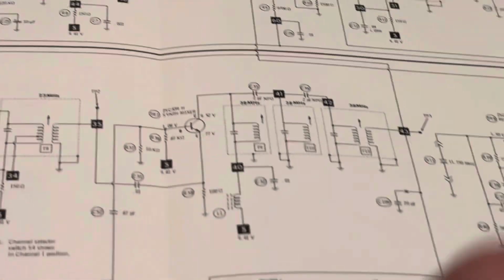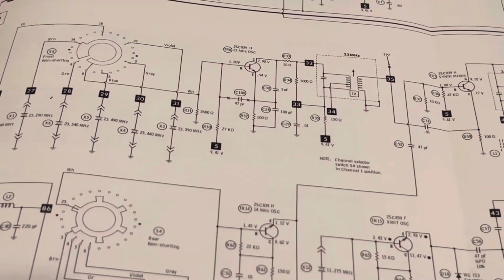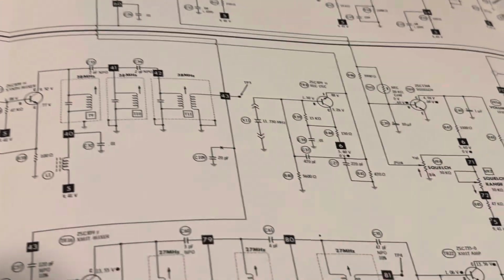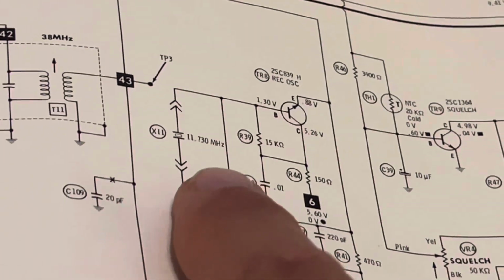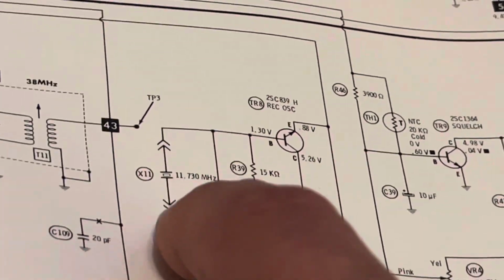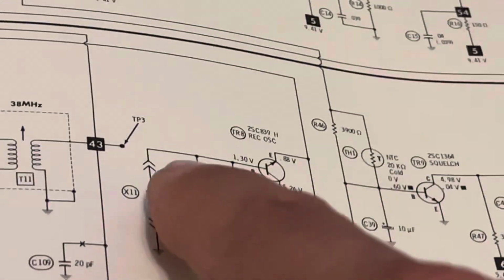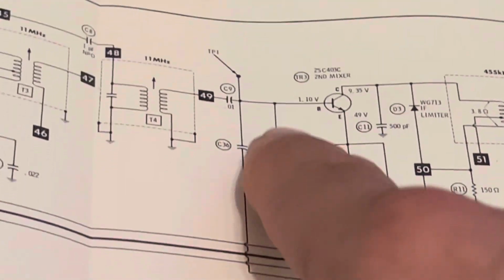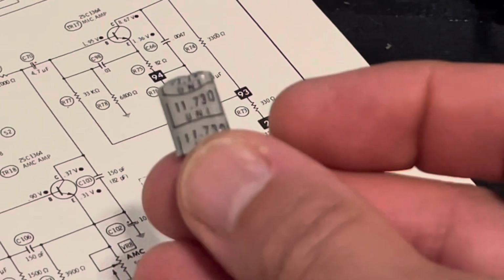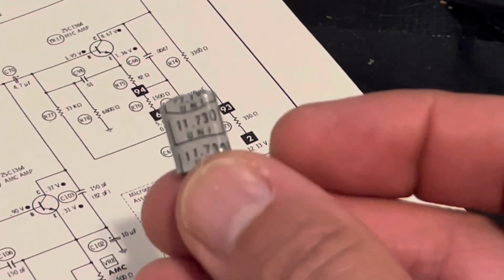So I started looking at the schematic and said to myself, what is common amongst all 23 channels on receive? And that brings us to this crystal right there. And this transistor here, once that 11.730 megahertz signal is amplified, gets fed up right to here, and then bam, that's where everything fell apart. So pull this crystal out, which is right here, and check this on the oscilloscope. I can zoom in on it. There we go. And it's definitely just dead as a doornail now.